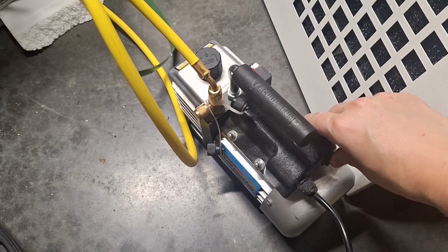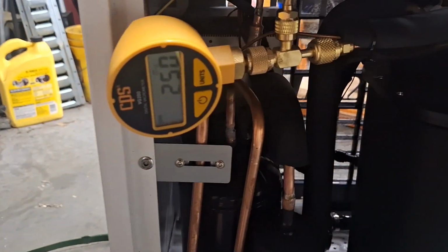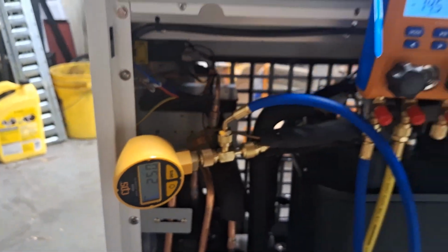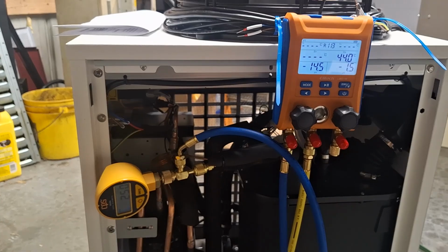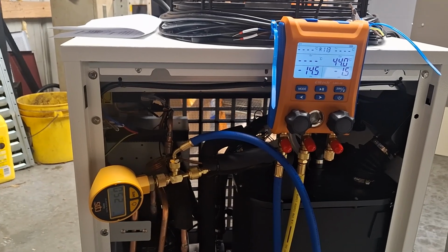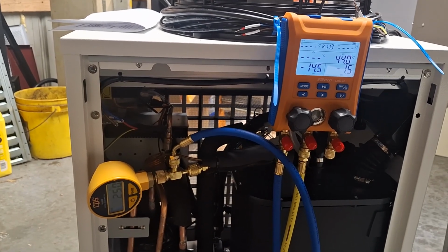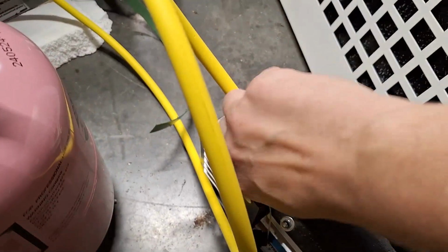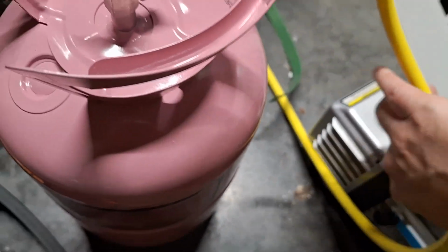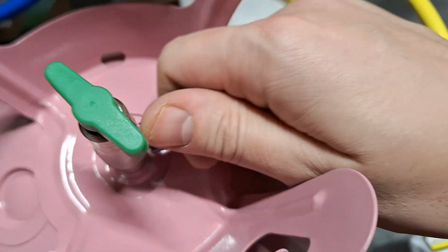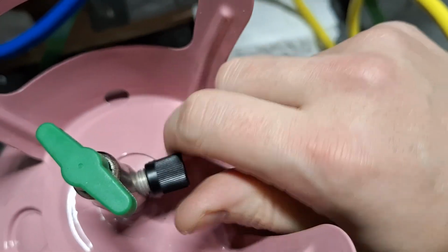There you just saw me cut the vacuum pump off at the manifold gauge by turning the valve and closing it off, so the vacuum remains but the vacuum pump is basically disconnected. Then you disconnect the yellow hose from the vacuum pump, and we'll take that same hose and put it on the R410A tank here.